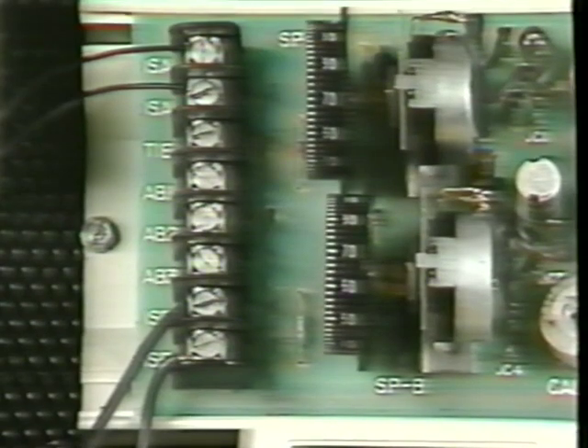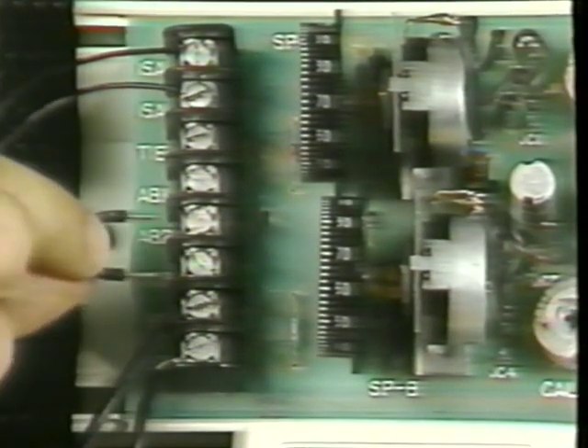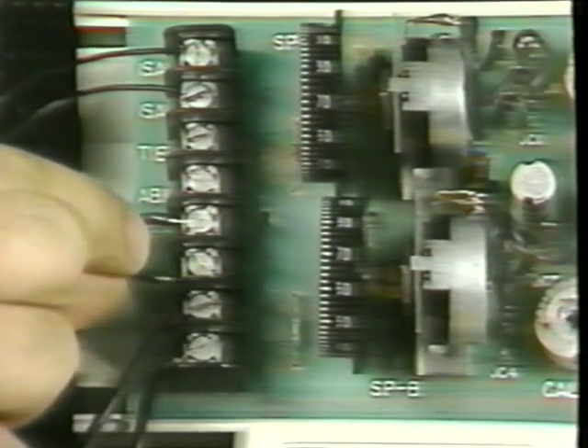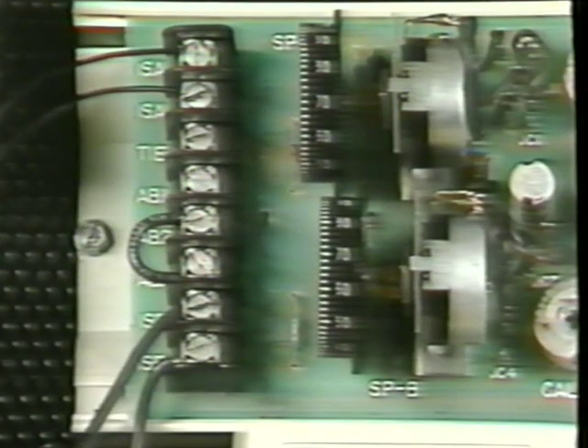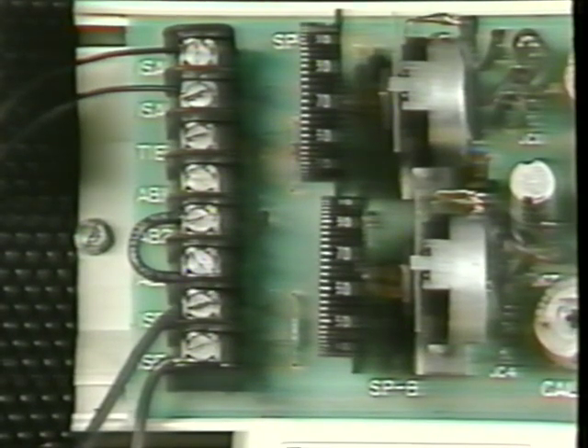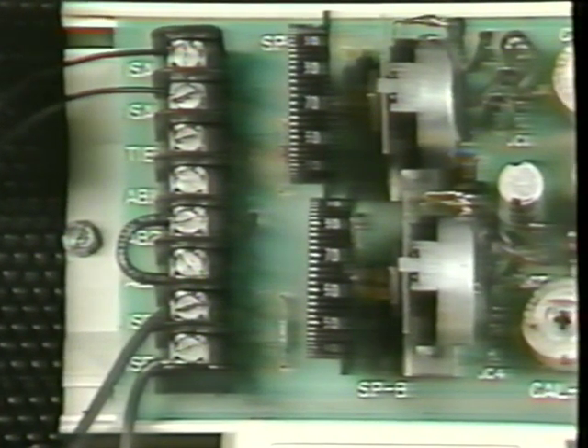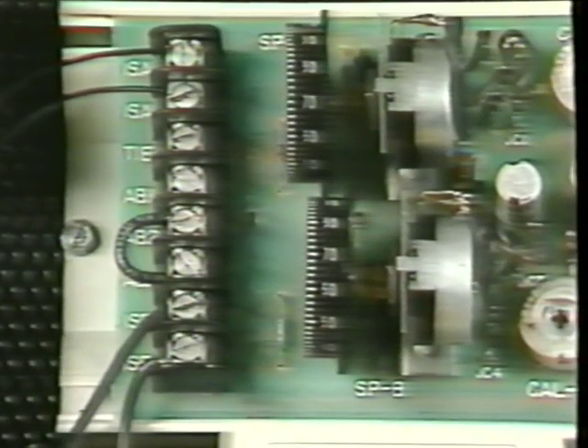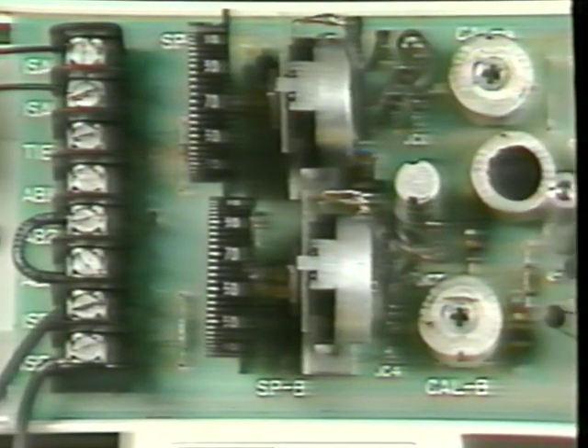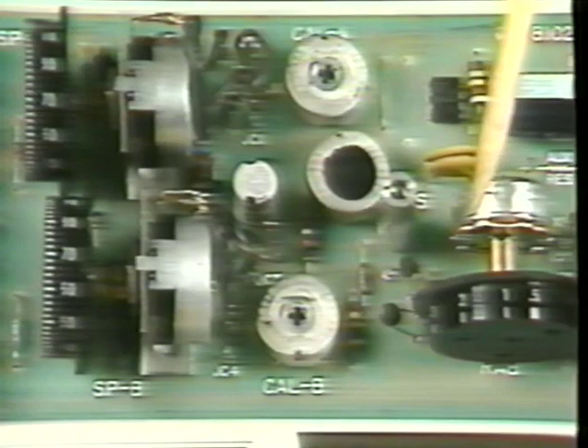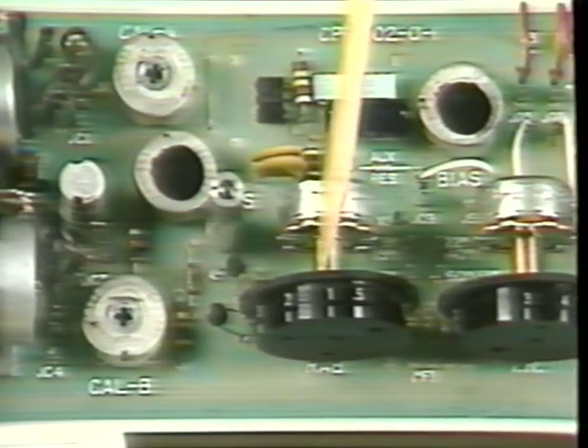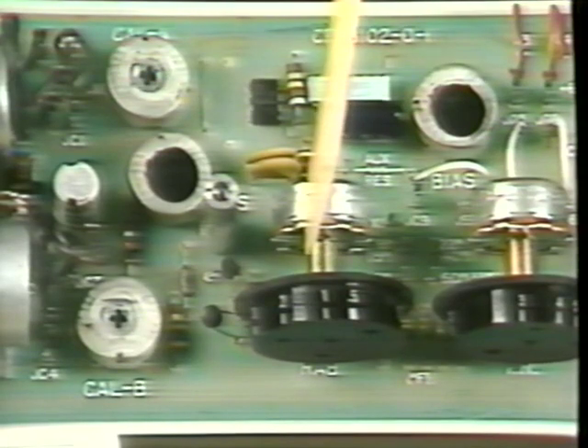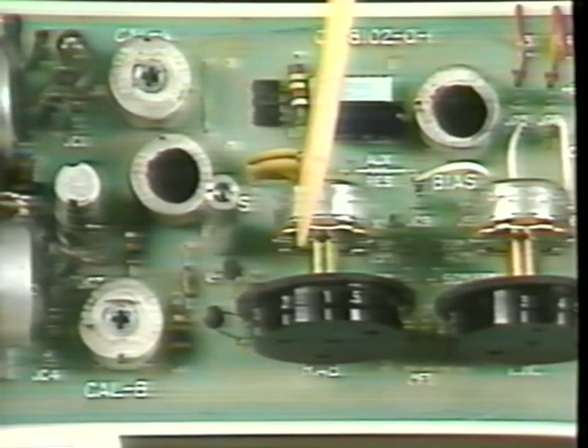However, if there is a B input, leave the set point A at the ambient and now restore input B by adding the AB2, AB3 jumper. Then repeat the steps described for the calibration of input A, with one addition. Whatever the ratio required for the application, during calibration, the ratio adjuster must be set at 1. Then, following calibration, it can be readjusted to the desired ratio.